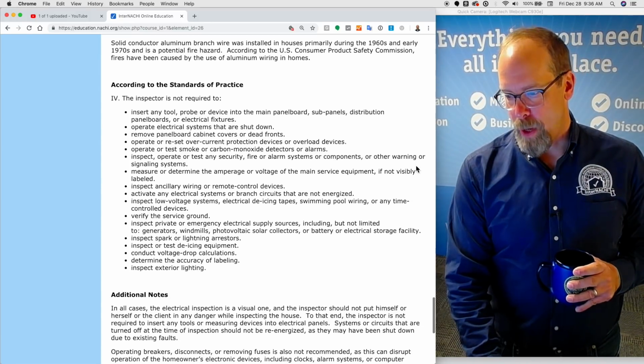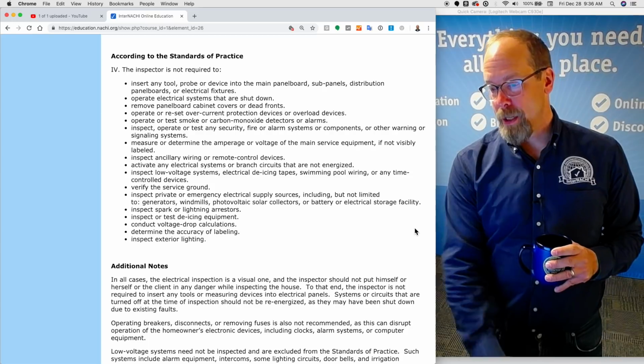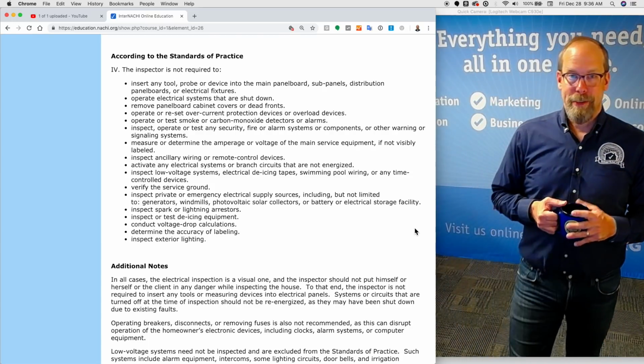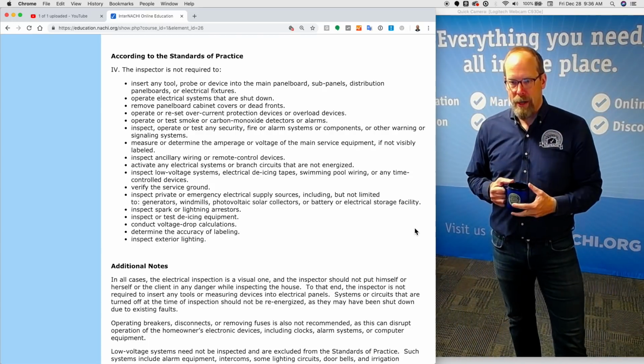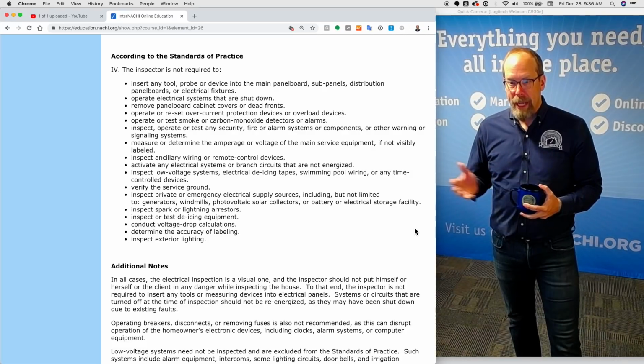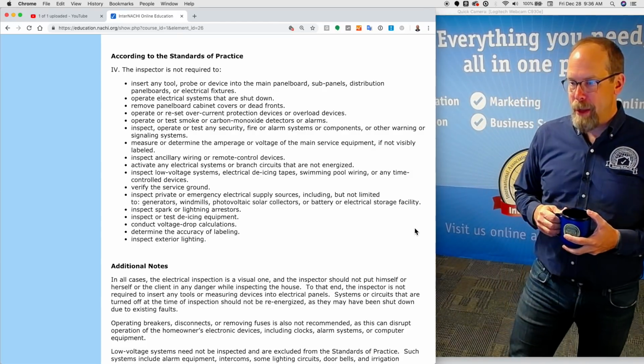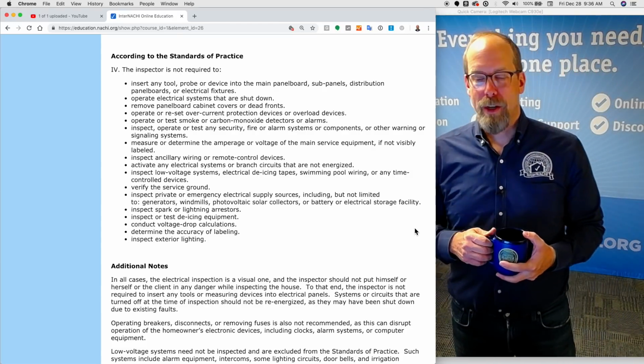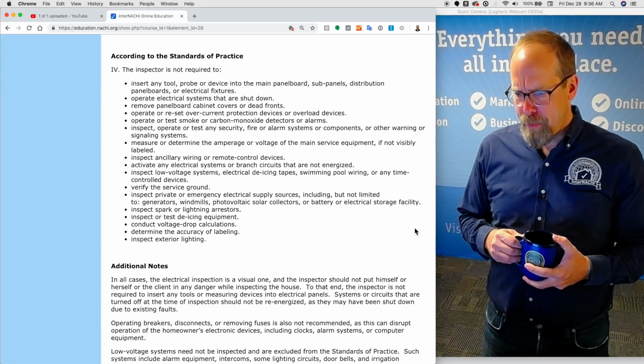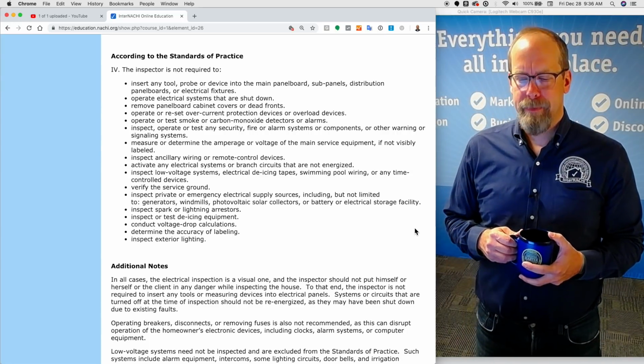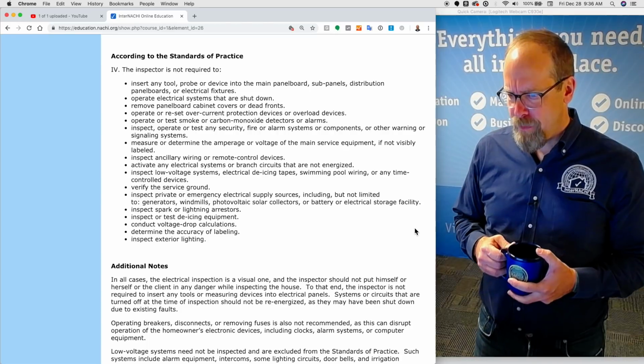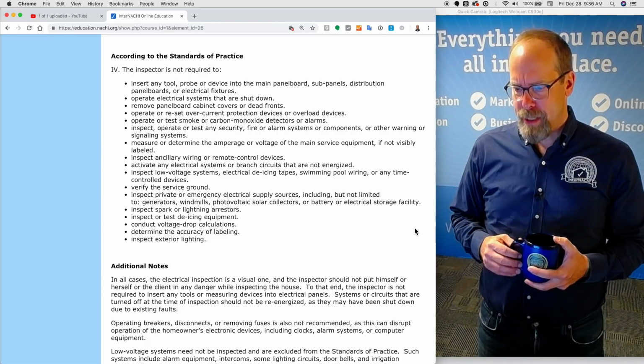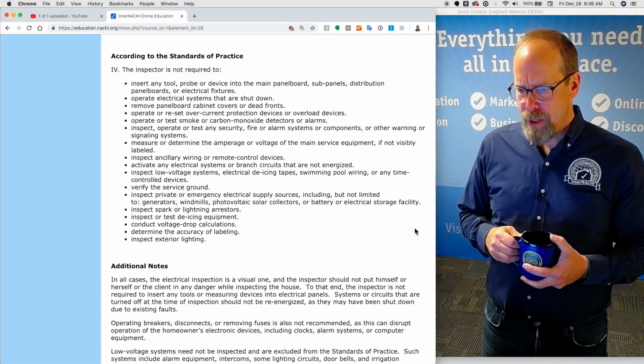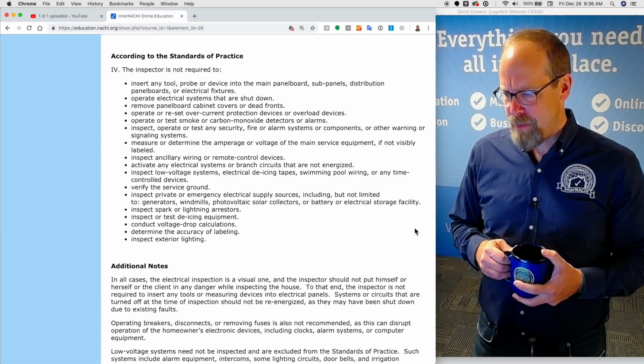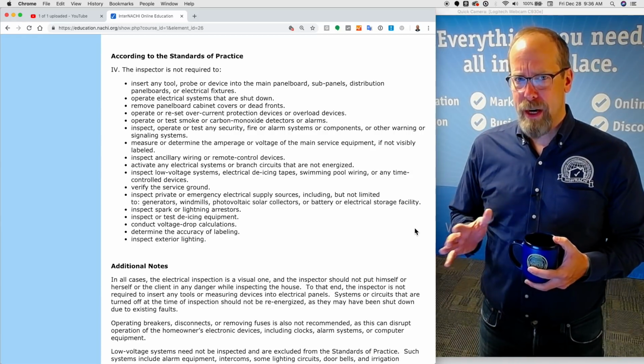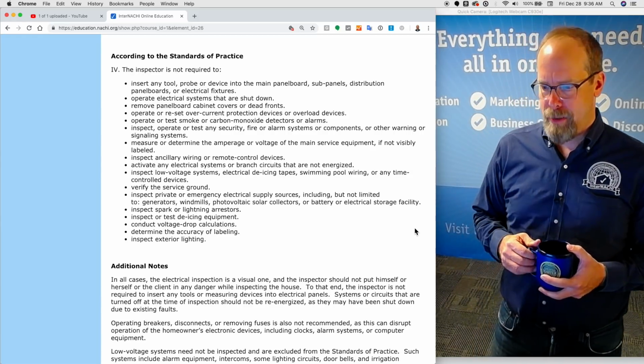Now, what are you not required to inspect? Well, according to the standards of practice, there's a lot. The inspector is not required to insert any tool, probe, or device into the main panel board, subpanels, or any fixtures at all. You're not required to operate electrical systems that are shut down. You're not required to remove panelboard cabinet covers or dead fronts. You're not required to operate or reset overcurrent protection devices and overload devices. You're not required to do it, and you really shouldn't. You should never do that.